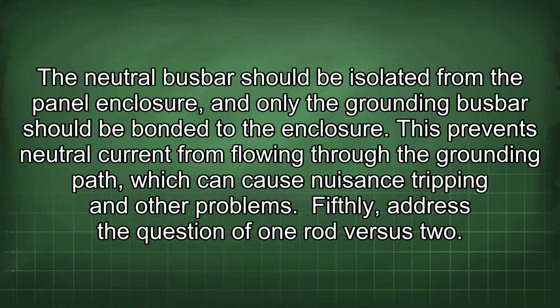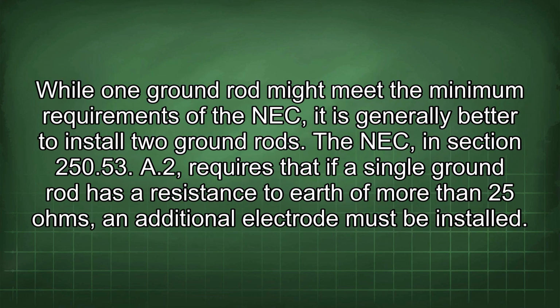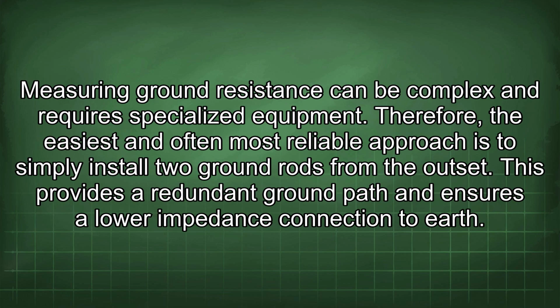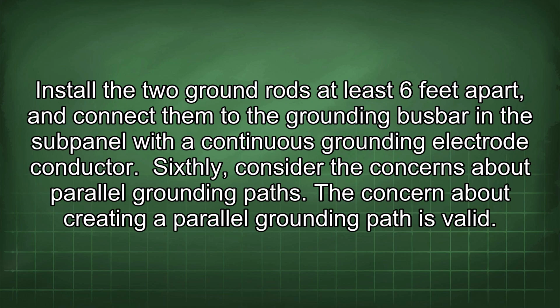Fifthly, address the question of one rod versus two. While one ground rod might meet the minimum requirements of the NEC, it is generally better to install two ground rods. The NEC, in section 250.53(A)(2), requires that if a single ground rod has a resistance to earth of more than 25 ohms, an additional electrode must be installed. Measuring ground resistance can be complex and requires specialized equipment. Therefore, the easiest and often most reliable approach is to simply install two ground rods from the outset. This provides a redundant ground path and ensures a low impedance connection to earth. Install the two ground rods at least 6 feet apart and connect them to the grounding busbar in the subpanel with a continuous grounding electrode conductor.